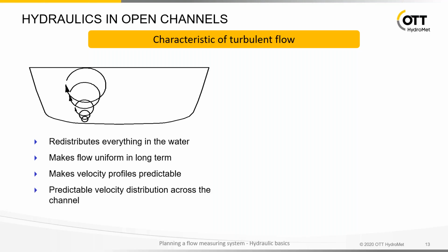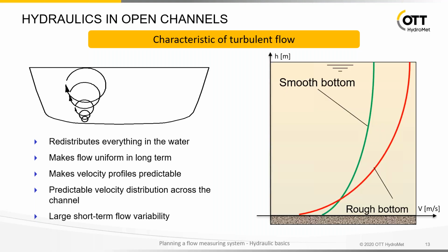You have a predictable velocity distribution also across the channel from the left to the right bank, and you have a large short-term flow variability, which means if you go to a single point in your water cross-section and you are measuring the velocity, then you have a lot of variations. This is also the reason why, for example, in portable flow meter applications, we are measuring with a certain time, for example, for magnetic inductive probes or for mechanical type meters, the minimum measurement time is 30 seconds to get a good average due to this short-term flow variability. If you look at the velocity distribution in turbulent flow conditions, you see it depends on the roughness of the bottom how the velocity distribution looks.